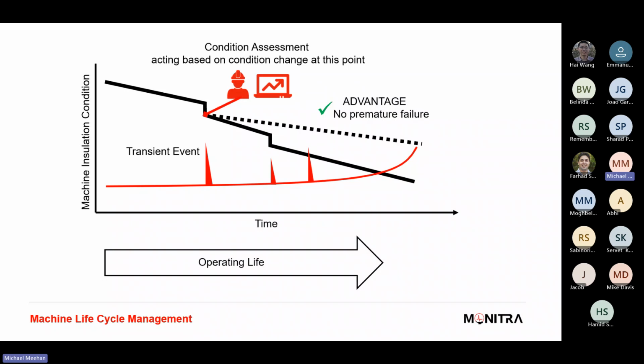Some of the preventative options could be lubrication systems and analysis of the oils, filtering systems on those oils. So you start to become more preventative in your approach and less reactive and less time-based. And then we want to look at predictive as well. That's where you can do the MCSA for the HV machines, looking at your motor current signature analysis, which is an online condition monitoring tool for any potential rotor issues.